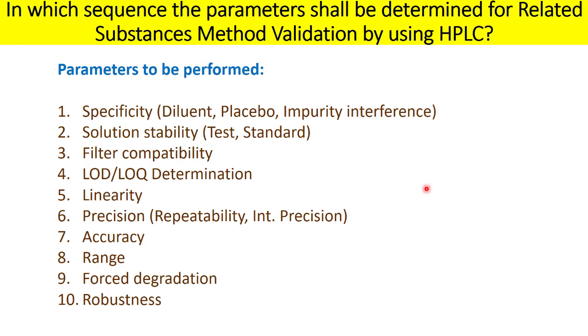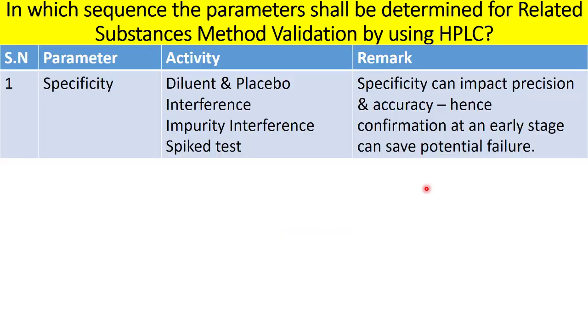According to my knowledge, you can consider this sequence for performing the various parameters. I will talk about the reason behind putting these parameters into this particular sequence. I will explain each parameter, the activity to be performed, and very importantly, why this parameter has to be performed in that sequence. I propose to perform specificity as the very first parameter during the related substances validation.